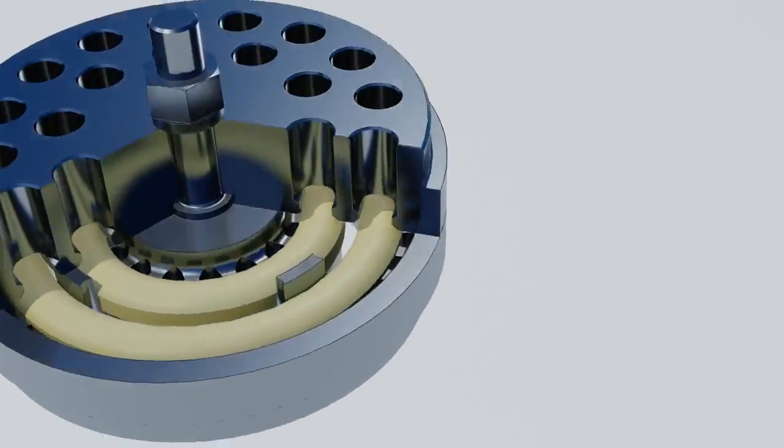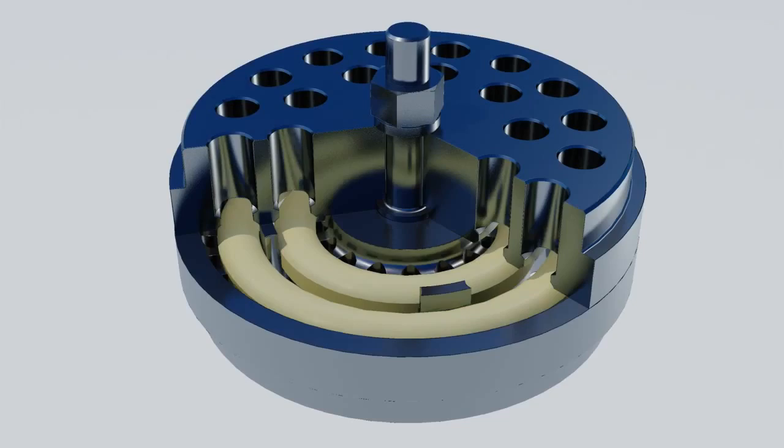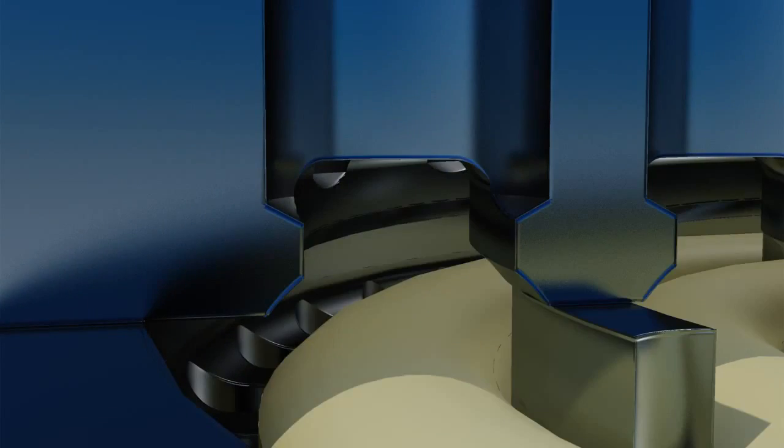Reliability starts with an advanced valve ring design. Radiused disc valve rings have precise dimensions that exactly match the radii of the seats. This means the rings and seats are self-aligning, ensuring good conformability throughout a wide range of operating temperatures.